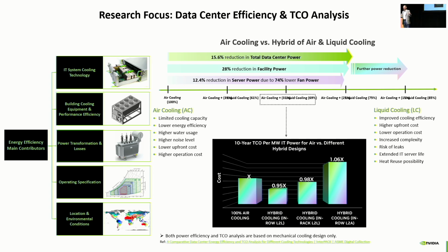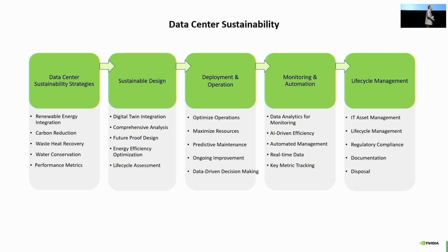That transition becomes cost saving. If I eliminate chillers and our chips use warm water cooling, I'm able to remove heat with liquid as opposed to air. We can get up to a 12% reduction in total server power because we're eliminating fans, 28% reduction in facility power, 15% reduction in total data center power. So I'm eliminating fans, reducing dependency on chillers, and surgically removing heat with much higher power utilization efficiency than air cooling. That's why liquid cooling means lower costs, both in installation, operation, and efficiency.